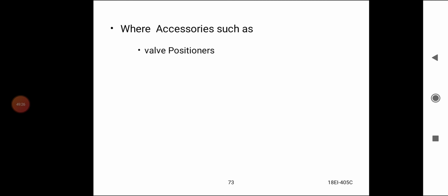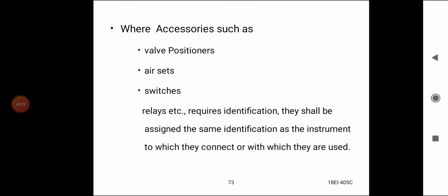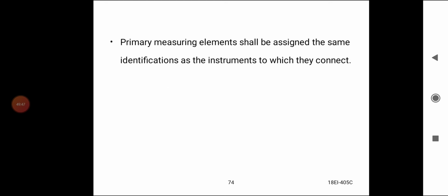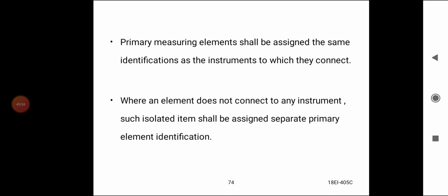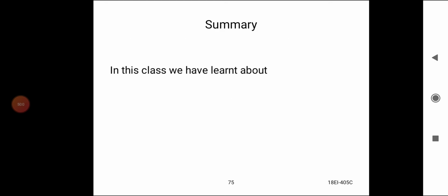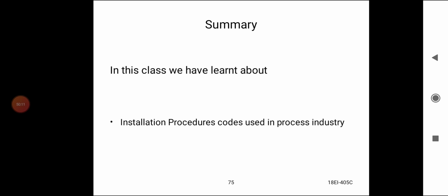Where accessories such as valve positioners, air sets, switches, relays, etc. require identification, they shall be assigned the same identification as the instrument to which they connect or with which they are used. Primary measuring elements shall be assigned the same identification as the instruments to which they connect. Where an element does not connect to any instrument, such isolated items shall be assigned separate primary element identification. Summary. In this class we learned about installation procedure and codes used in the process industry.